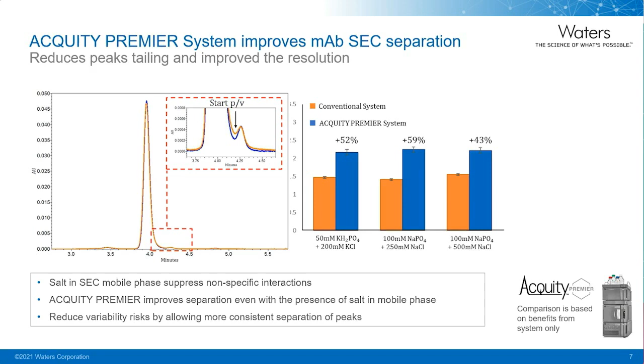This experiment looks at the benefit of just the ACQUITY Premier UPLC system versus an H-Class Plus Bio binary system without the benefit of Premier columns. Traditionally, to address non-specific interaction problems in SEC, salt is added to suppress the interactions. Here in this experiment, the half antibody peak is better resolved from the main peak due to reduced tailing from the main peak, resulting in improvements in peak to valley ratio. This experiment shows that even after adding salt to suppress non-specific interaction on a biocompatible system, a user could further improve separation with an ACQUITY Premier UPLC system.